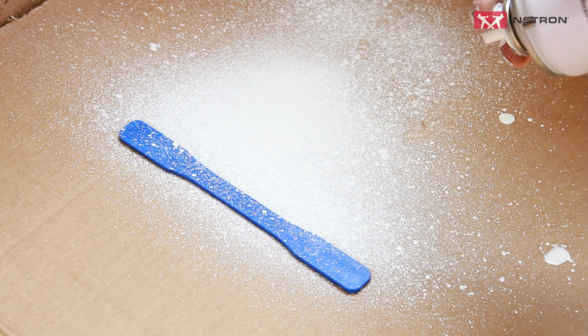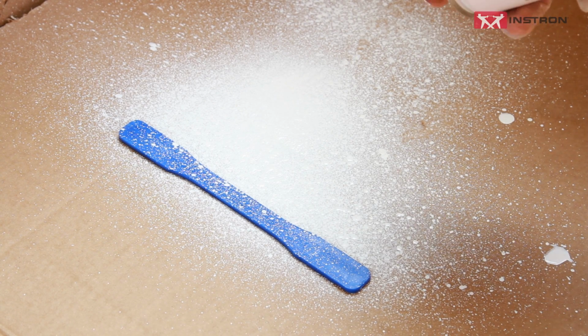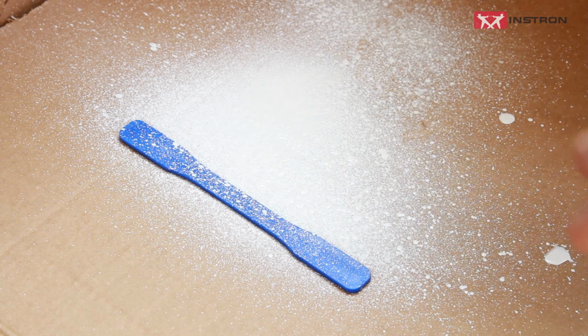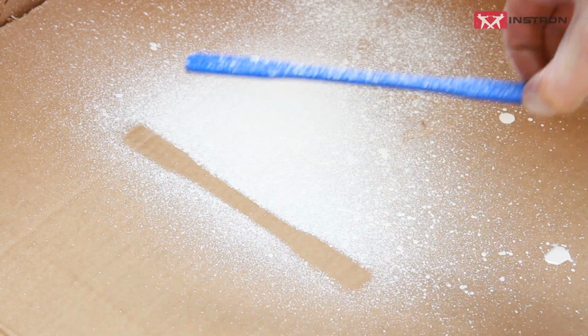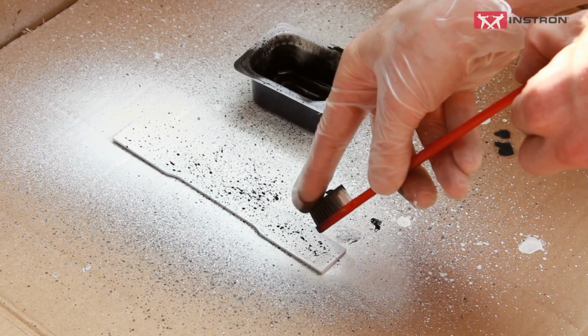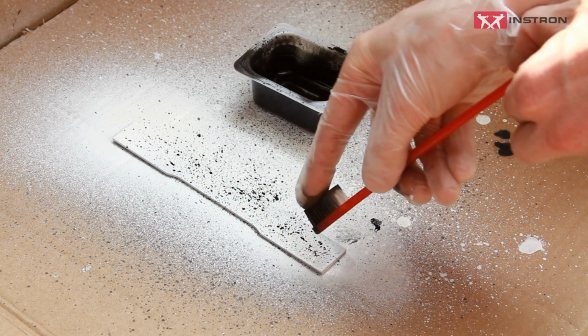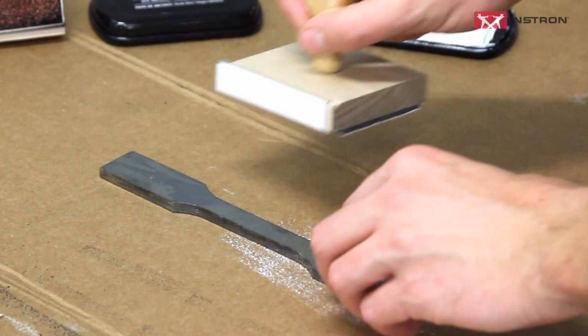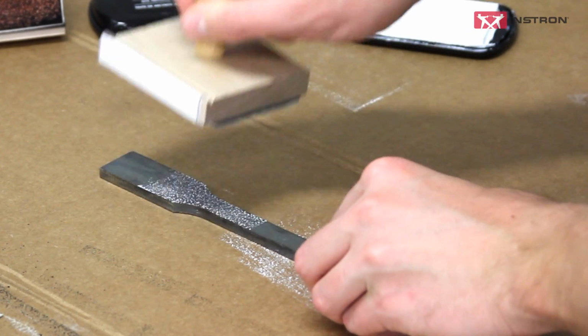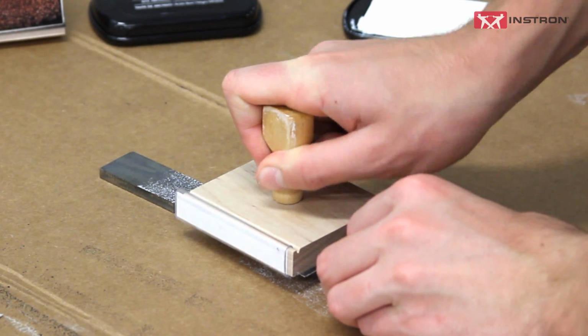In order to perform DIC on a materials testing specimen, it must be marked with a random pattern of contrasting marks. Traditionally, specimens are marked by creating a speckle pattern using spray paint or by flicking a toothbrush loaded with ink or paint. Stamps can also be used to both quickly and easily mark the specimen with a random pattern.